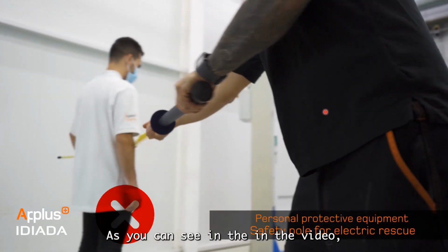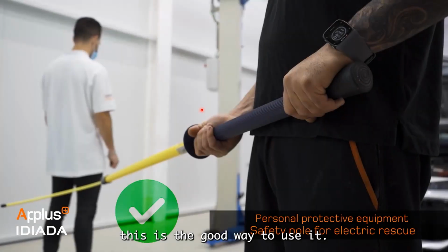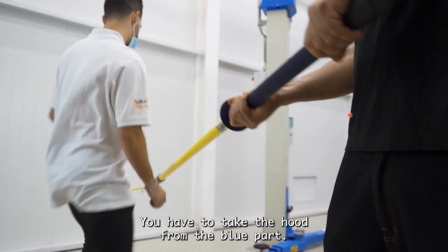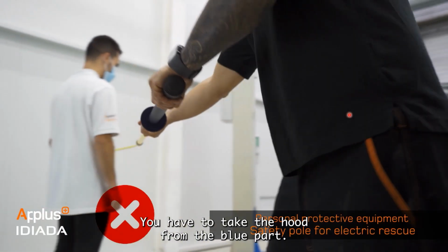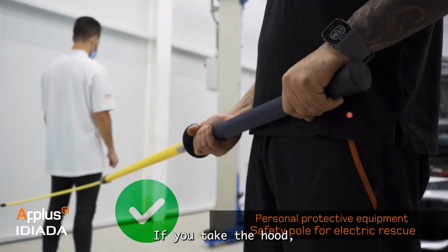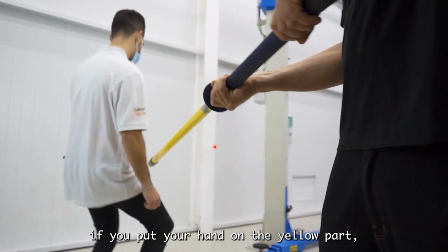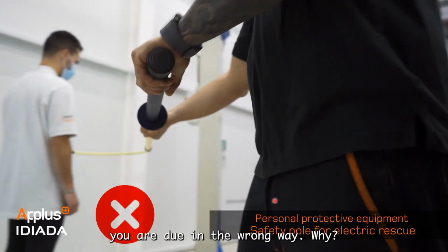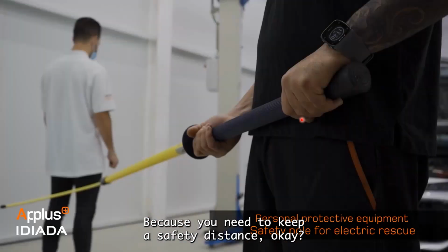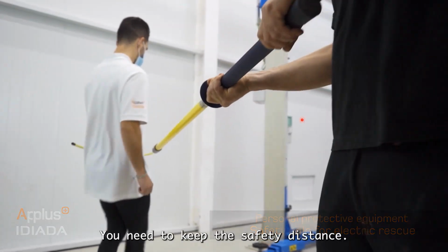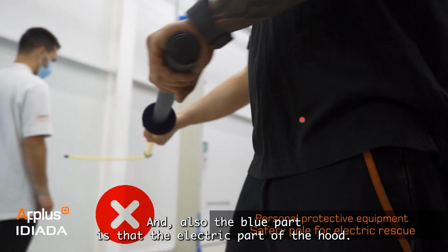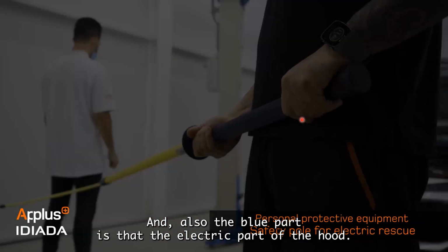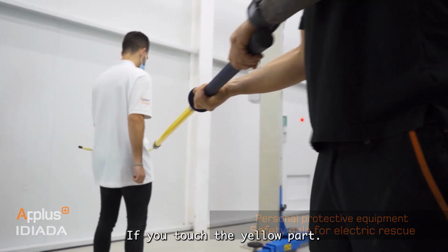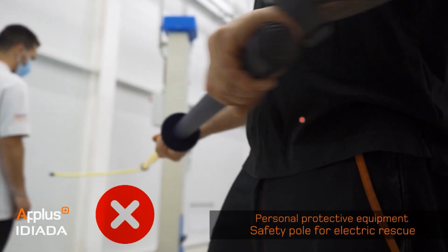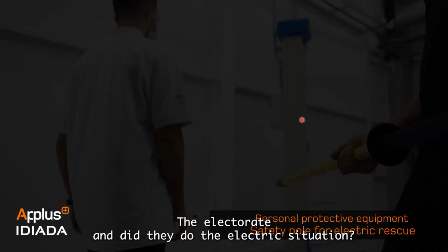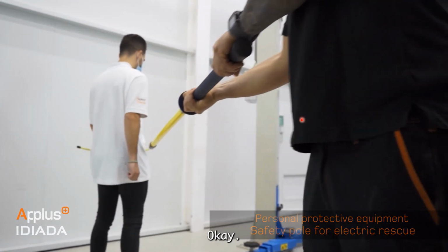As you can see in the video, this is the correct way to use it - you have to take the hook from the blue part. If you put your hand on the yellow part, you're doing it the wrong way, because you need to keep a safety distance. The blue part is the dielectric part of the hook - if you touch the yellow part, the dielectric protection is not guaranteed.